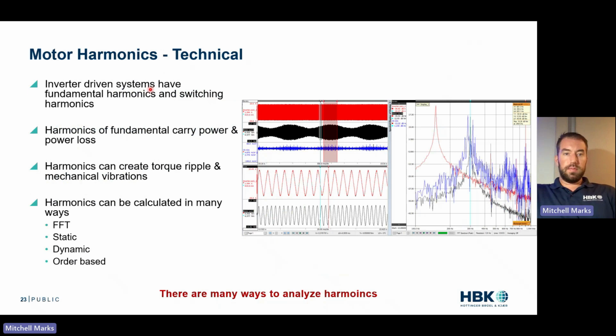So inverter-driven systems have fundamental harmonics and switching harmonics. Those are two different things. Most of what I'm going to talk about today is the fundamental. If you measure high enough, you can also do these things with the switching. Harmonics of the fundamental carry power and power loss. If you filter out your harmonics, you will get a wrong power value. I can assure you of that.